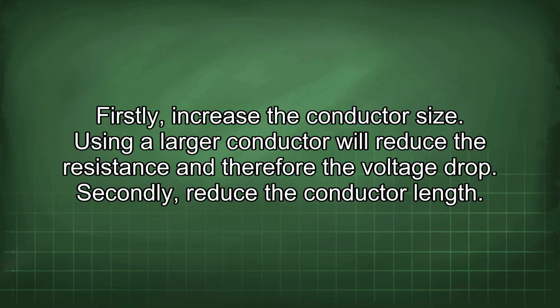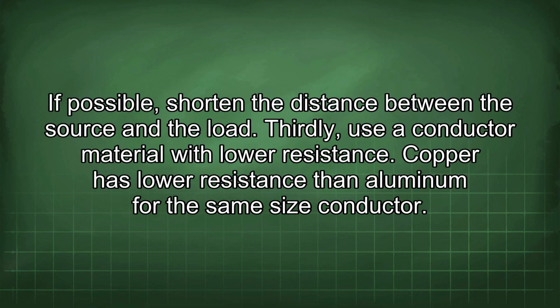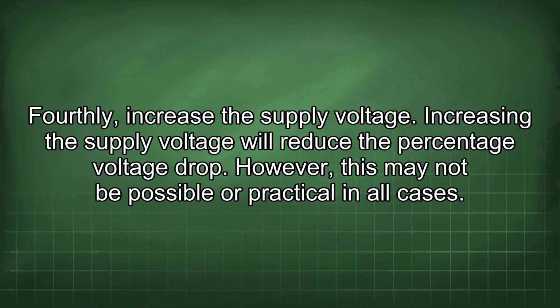Secondly, reduce the conductor length. If possible, shorten the distance between the source and the load. Thirdly, use a conductor material with lower resistance. Copper has lower resistance than aluminum for the same size conductor. Fourthly, increase the supply voltage. Increasing the supply voltage will reduce the percentage voltage drop. However, this may not be possible or practical in all cases.